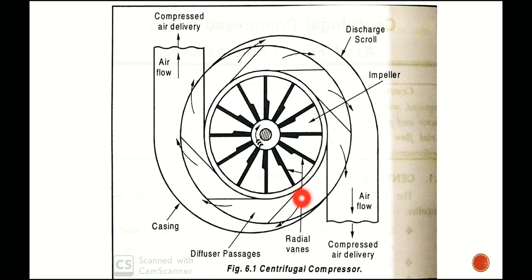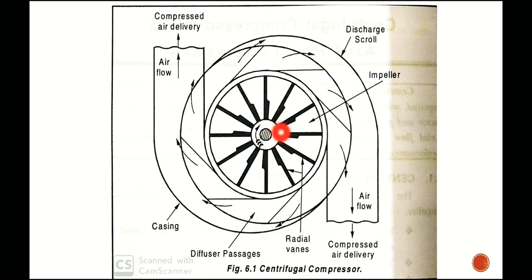The diffuser converts high velocity into high pressure. The air exiting the diffuser has very low velocity and very high pressure. When the pressure is raised above atmospheric, the air can be delivered. Half the pressure rise is achieved by the impeller and the remaining half is achieved by the diffuser.